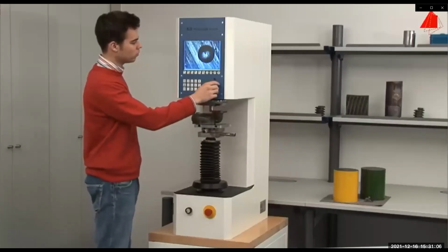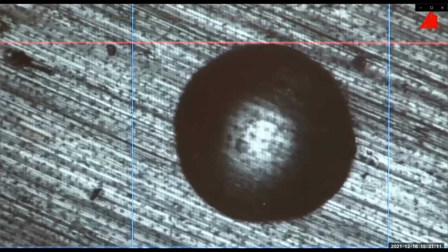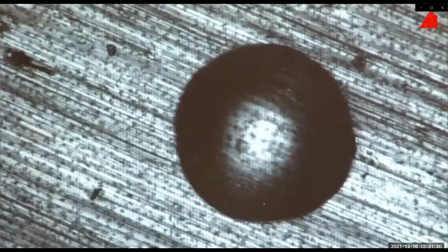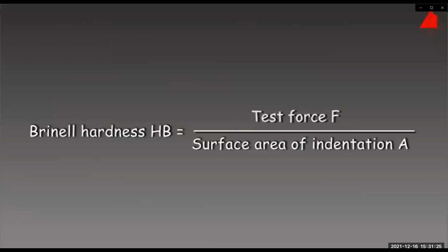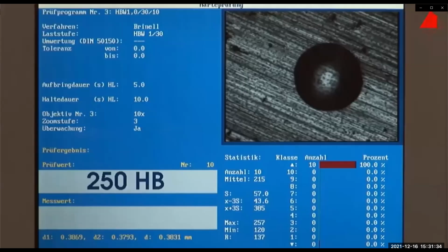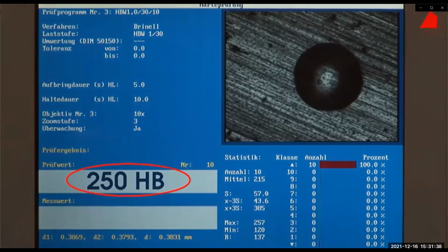The indentation can now clearly be seen on the monitor. With the control knob, the tester places 4 measuring lines on the edges of the indentation to measure its diameter. That's it. The testing machine can now calculate the Brinell hardness. The hardness value is defined as test force F in the old unit kilopond divided by the area of the indentation A in square millimetres. The result is displayed on the bottom left-hand corner of the screen and amounts to 250.